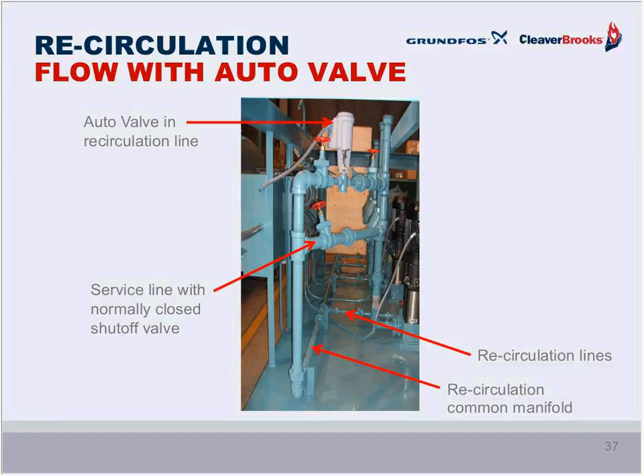When you've got that recirc line, there's always return flow to the feed tank. And that happens, importantly, even when the pump is running at its duty point, which is at low head and far away from deadheading. But you're still getting constant recirculation flow when it's not really needed, and that amounts to wasted energy. So one way you can get around that is by installing this auto valve in the recirculation line.